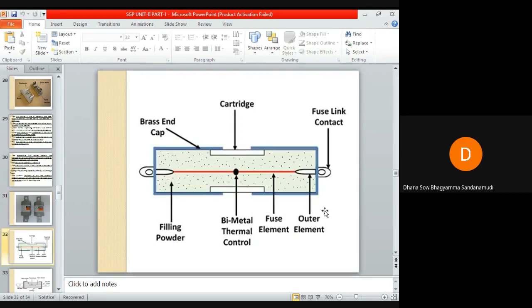So whatever limitations are there in the semi-enclosed KitKat type fuse, those limitations are overcome by using this HRC cartridge fuse. One of the limitations is that it can interrupt only low voltages or low currents, and the breaking capacity of that KitKat type fusing element or the fuse is uncertain. Because of low current interrupting capacity and because of uncertain breaking capacity of the semi-enclosed rewirable fuse, the HRC cartridge fuse is preferable. Okay, in order to overcome those limitations, the HRC cartridge fuse is preferable when compared to that.